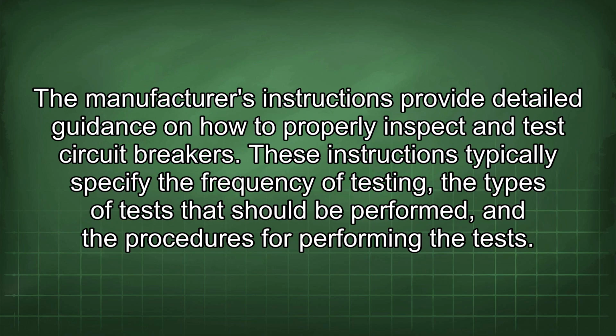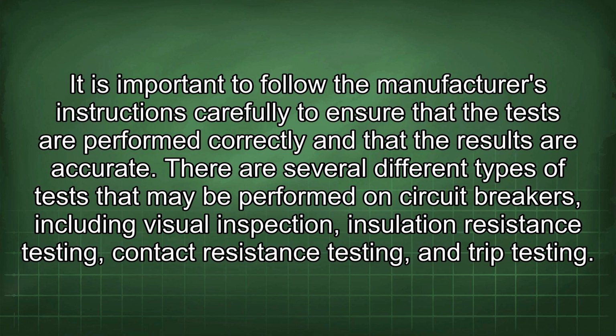The manufacturer's instructions provide detailed guidance on how to properly inspect and test circuit breakers. These instructions typically specify the frequency of testing, the types of tests that should be performed, and the procedures for performing the tests. It is important to follow the manufacturer's instructions carefully to ensure that the tests are performed correctly and that the results are accurate. There are several different types of tests that may be performed on circuit breakers, including visual inspection, insulation resistance testing, contact resistance testing, and trip testing.